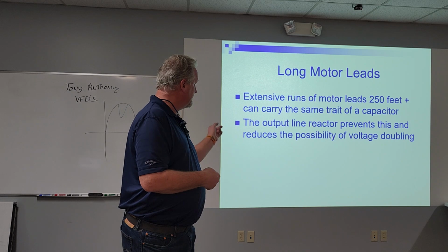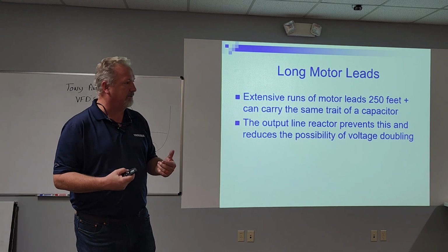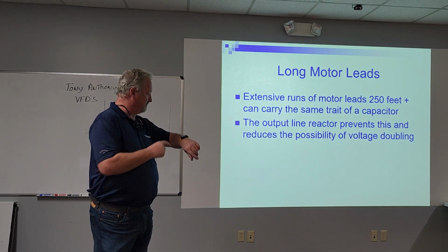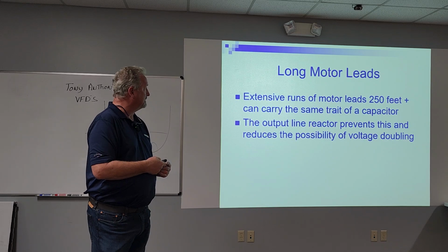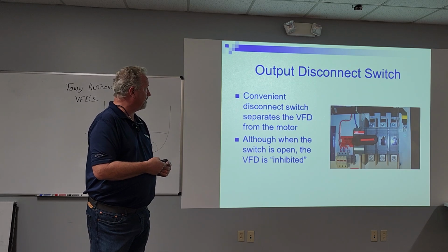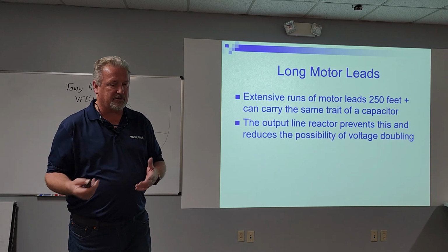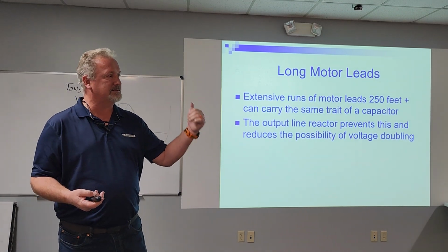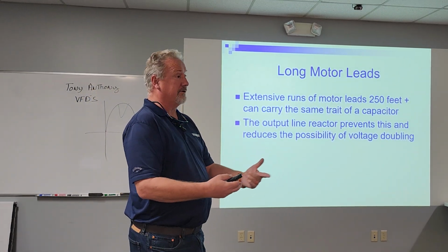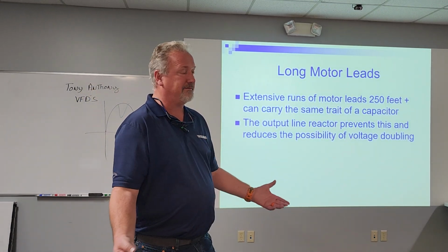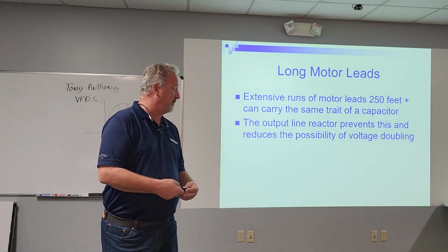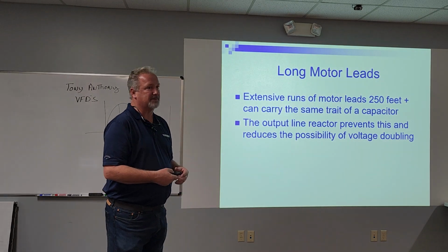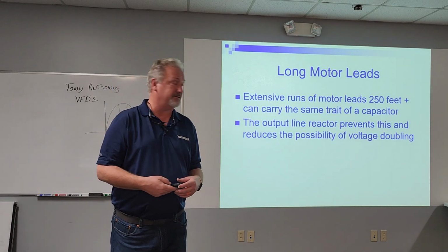It prevents what we call voltage doubling, and that's just based off how the drive works. I'm not really getting into that. So that's when you would use a load reactor: long distances, multiple motors, weird trips that you can't figure out why they're happening, when the motor's a good bit away usually. Load reactors sometimes will clear all that up or prevent issues.